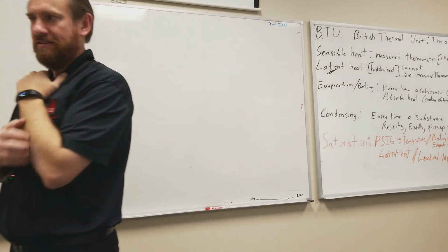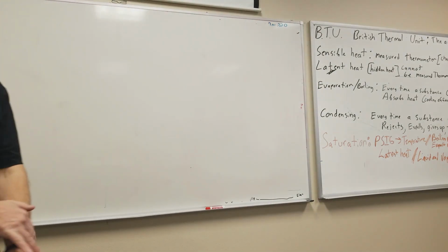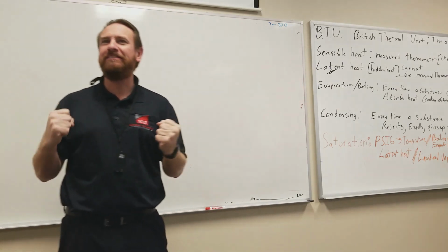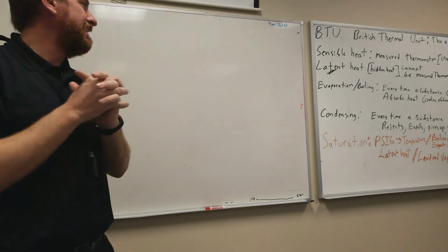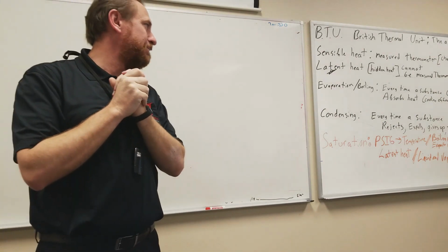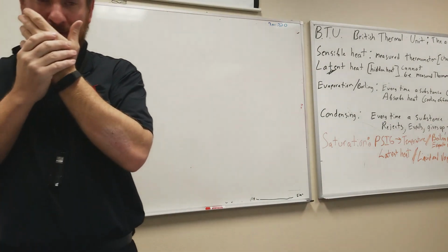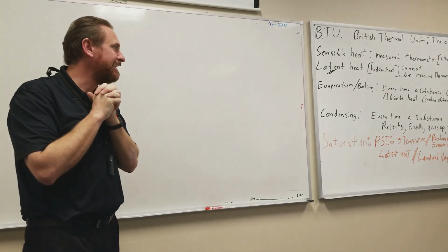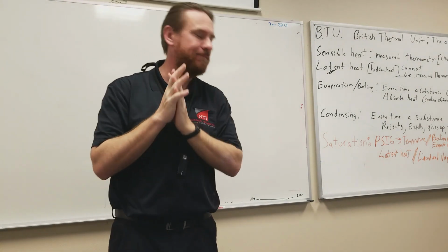All right, and then very, very, very important, saturation. PSIG, converted temperature. That is the most important. It needs to be, bam, immediately, PSIG, converted temperature. And then the other words that it means? Boiling point. Boiling point, yes. Condensing point. Change of state, latent heat, liquid and vapor both exist at the same time.